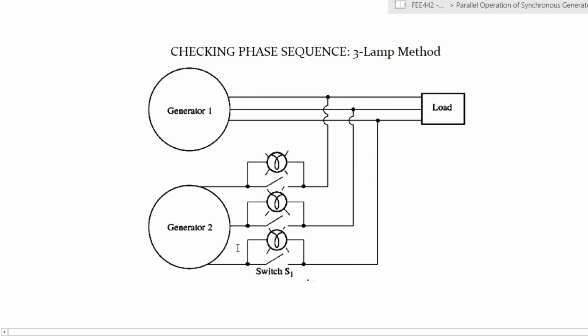So let's take this illustration. You have generator 1 supplying a load, and you want to connect generator 2 through switch S1. So we assume S1 is connected together so that it switches at once. And you want to check what is the phase sequence, or whether it is possible to connect to that system. Your system consists of generator 1 and the load, and the generator that you wish to connect is generator 2. Now we would have the setup as indicated here. You'd have lamps connected across the switch. One leg of the lamp would be connected to the system voltage, and the other would be connected to the generator voltage. The assumption, of course, is that your generator is running at the required frequency and voltage and ready to go, but you just need to check the phase sequence.